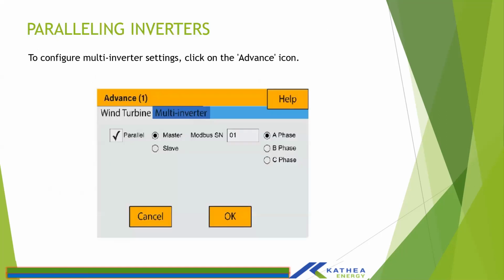And then our next subsection will be paralleling inverters. SunSynk inverters can be paralleled, that is, connected as multiple inverters. You can build any system size of preference, whether in a single-phase or three-phase scenario. So if you intend to parallel inverters, which is basically connecting more than one inverter, you would need to activate that in settings, advanced, and then multi-inverter.